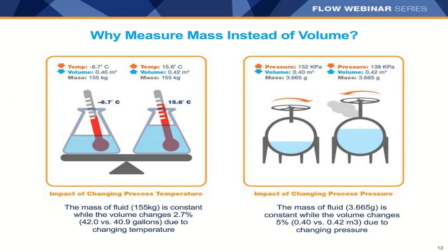Why measure mass instead of volume? An increase in temperature causes density to go down, which results in increased volume — the higher the temperature of the fluid or gas, the greater the volume it will occupy. However, the units of mass stay the same when temperature changes, because mass does not change with temperature. So if you're measuring in volume and temperature increases, volume goes up; measuring in mass, it stays the same.